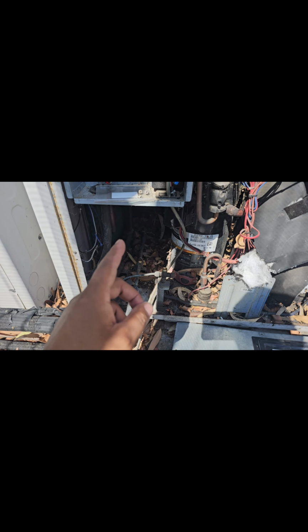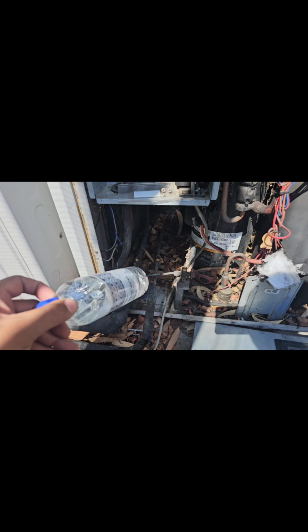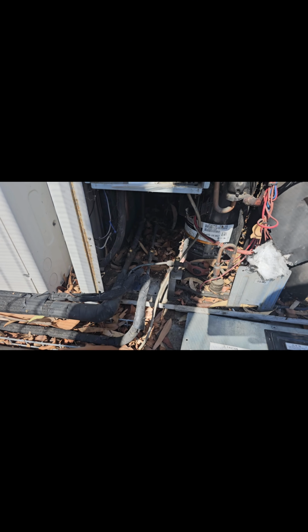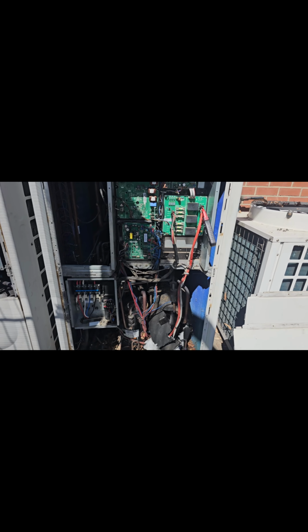So yeah, what I've done now is I've proceeded to open the valves. The oil balance line was open, so that was never isolated, but we opened our suction and liquid line, or discharge line, however you want to look at it. The expansion valves on these units are at the indoors. This is a VRF system, so the expansion valve is not at the condenser, which would then ultimately make this a liquid line. However, that is what it is. It's a high pressure liquid. So yeah, let's have a look.